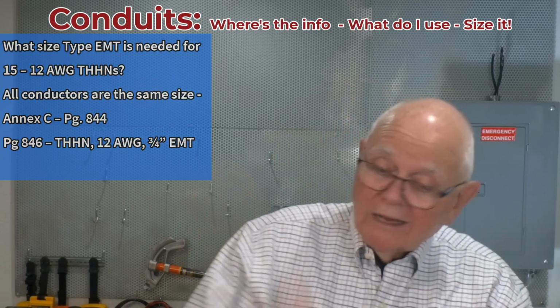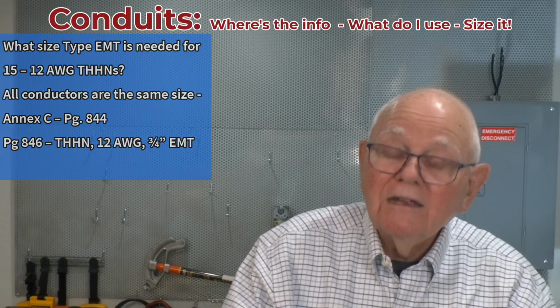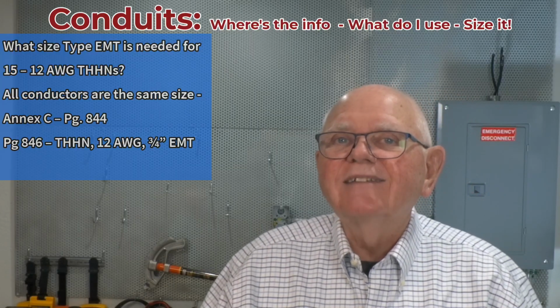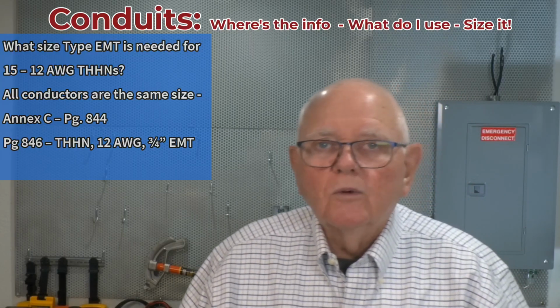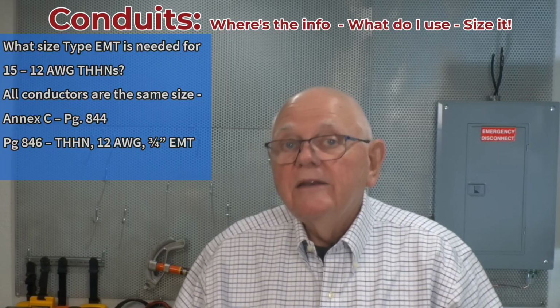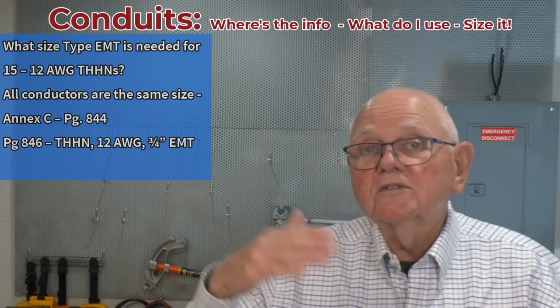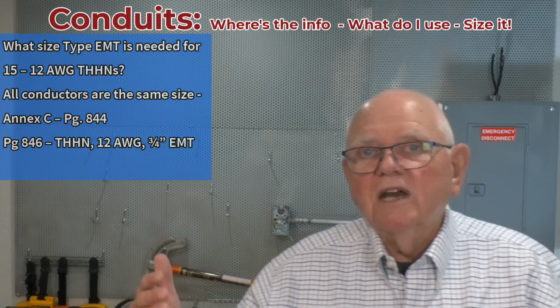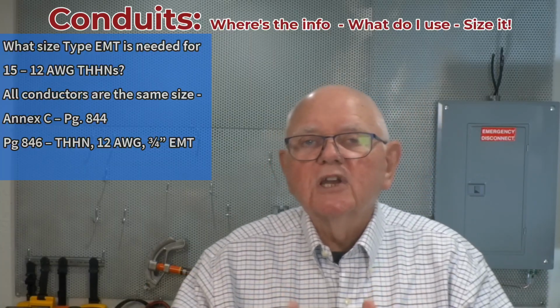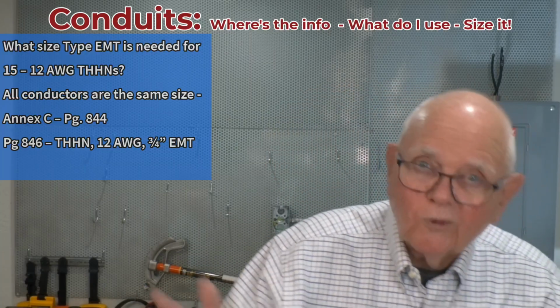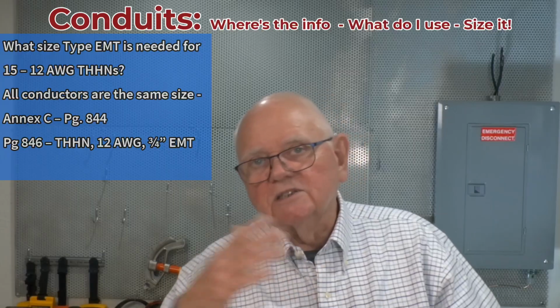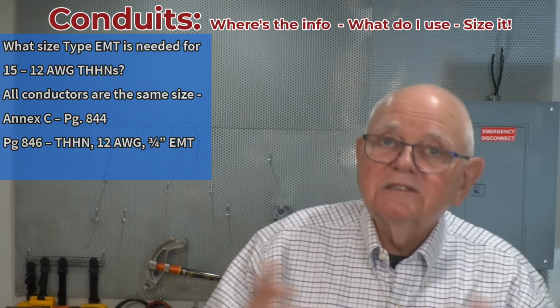How do I know that? I go to Table C1A and I look at the bottom and it tells me that. The bottom of each page will tell me what it means by compact stranding. Now, compact stranding I only use in certain larger size conductors, so you'll notice that the tables don't start, for instance, on number 14 or whatever. It might start on something like number 8. So there's going to be different tables.